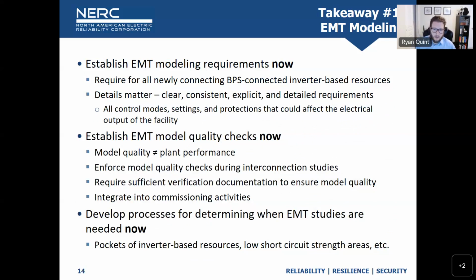We need to establish EMT modeling requirements now, not later. We've heard that from around the world - people wishing they had that model earlier at the time of interconnection, because now the plant has changed hands 5 times or the OEM is out of business and there's no way to get a good model for this plant. So establish those EMT modeling requirements now for all newly interconnecting IBRs, and I'd even take that further and say all newly interconnecting generation.